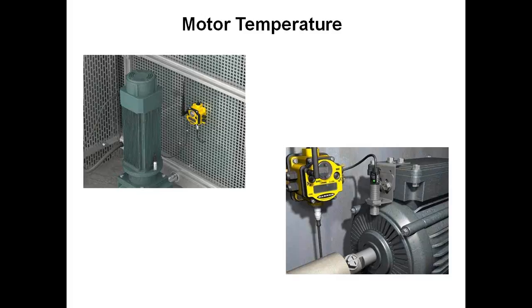Motor temperature is a really good one. With our standard nodes, you'll find these, some have 3 thermocouple inputs, some have 4. We can also do RTD. They play very well with the flex-powered battery. Since the thermocouples really don't pull much power, you could put a node out here with a battery module, and this guy would probably run 5 to 7 years on that battery. In some applications, the guys will come down with a thermocouple on the flange of the motor or a certain part.